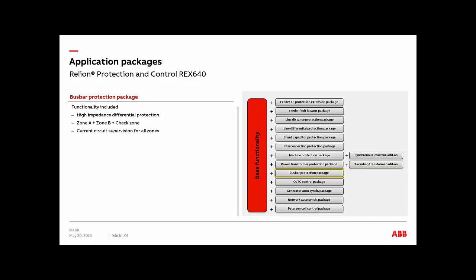Bus bar protection package. It's important to mention it is a high impedance differential protection. The relay does not have a low impedance. The only low impedance we have is the transformer 3-winding, which could be used. If we have a bus that has 3 terminals, you could use it that way as a low impedance.